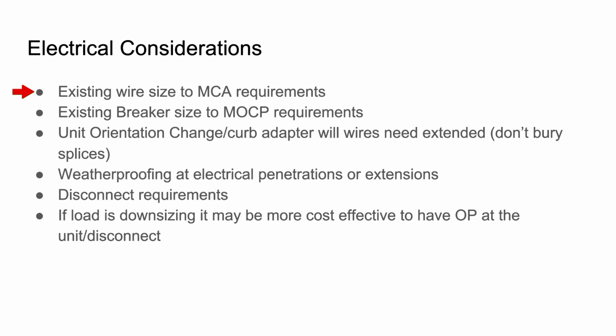And so you want to look at what your existing wire is, get the gauge of that wire. That'll correlate to a chart that gives you what amperage it's rated for. And if you ever see on a unit, it'll say MCA, or minimum circuit amps, and I think those are really the only two things it says there. That is how much that wire is rated for. And so you can't have a wire that's rated for less than that MCA rating on a nameplate.